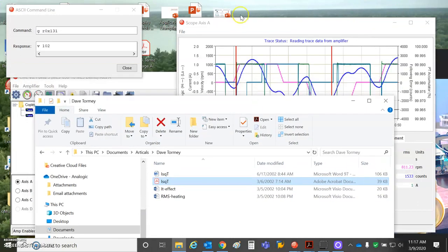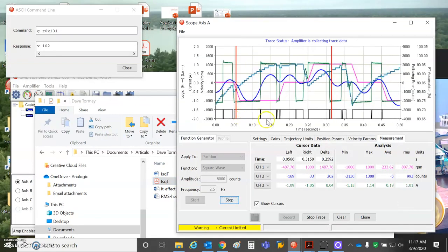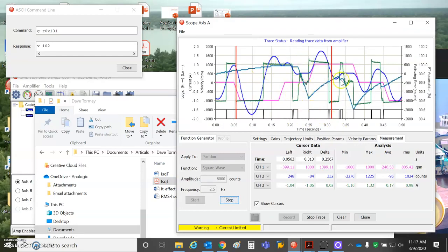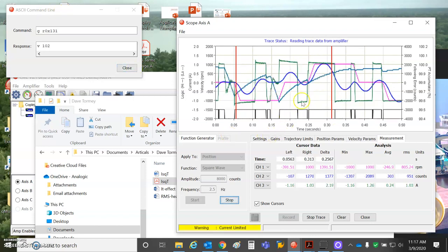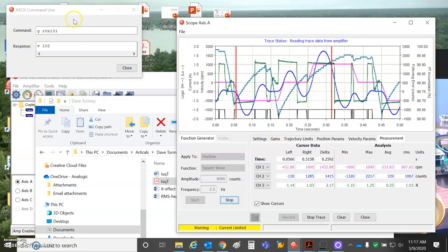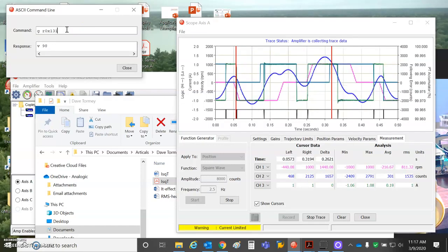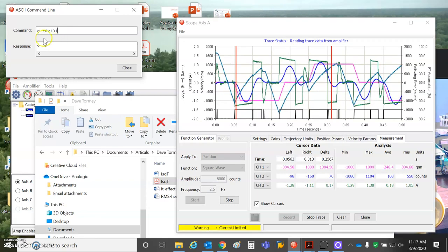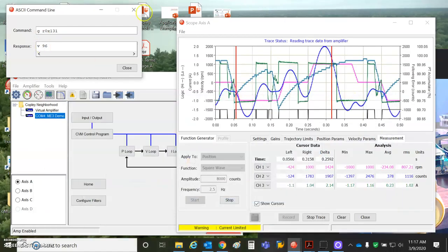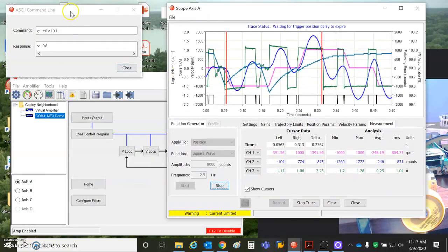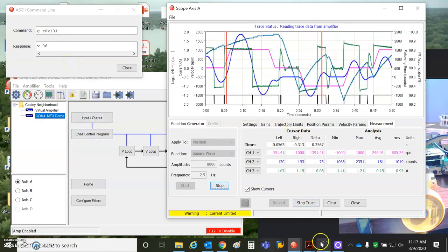What it's not doing is preventing us from having problems if you're at a continuous current limit constantly. Your following error, your motion profile suffers, and eventually you're going to get a following error under normal conditions. And again, we're current limiting constantly, and our RMS current is at an amp. And so that's the danger zone right there. So we can use this function or this feature in the drive to preempt something bad happening.